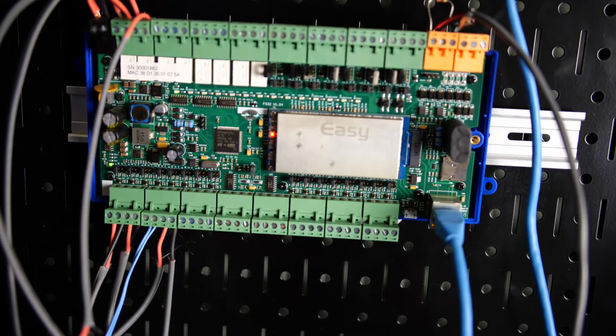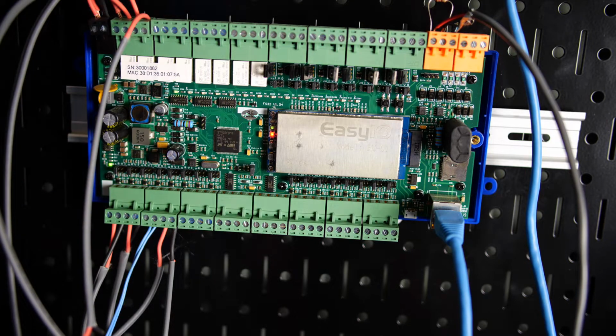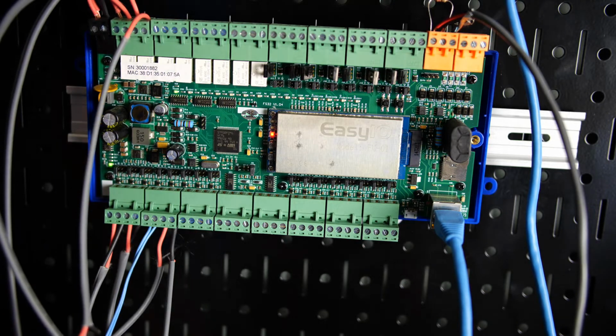Okay, so the important thing to note here is that when we are using these relays, as we're using internal relays, we want to make sure that we are passing through the appropriate voltage rated for our contacts there, because if we're passing through like 120 and it's not rated for 120 volts, we can actually destroy those. Also, we've got to be cognizant of the amperage. Now that's for internal. When it's external, this relay in a box, once again, this thing costs like $10. So you blow a $10 relay in a box, it's not that big of a deal. You blow a $400, $600 controller, it is a big deal.